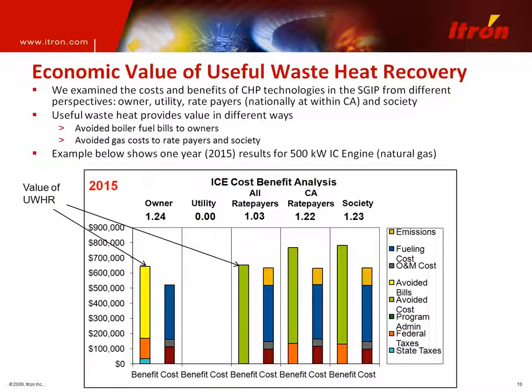So one of the points I want to make here is that we know that useful waste heat recovery has significant benefits. Good metering is really critical to being able to accurately identify, and then, as John had pointed out, you need to allocate those benefits, right? So this is critical on how you allocate them. Accuracy in your results is not just dependent on the precision or the accuracy of the metering. That's very critical, but you also have to take into account the variability of the heat recovery rate within the application. And you have to take both of those into account when you begin to talk about the certainty of results. And so good heat metering is critical to achieving that, but most importantly, a heat metering standard is essential.